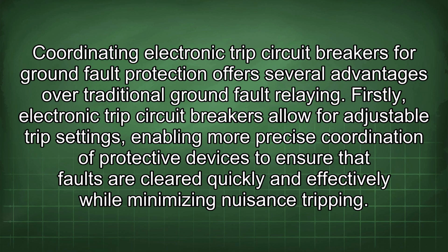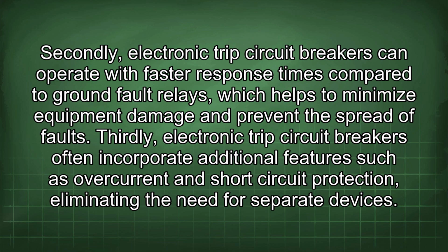Firstly, electronic trip circuit breakers allow for adjustable trip settings, enabling more precise coordination of protective devices to ensure that faults are cleared quickly and effectively while minimizing nuisance tripping. Secondly, electronic trip circuit breakers can operate with faster response times compared to ground fault relays, which helps to minimize equipment damage and prevent the spread of faults.